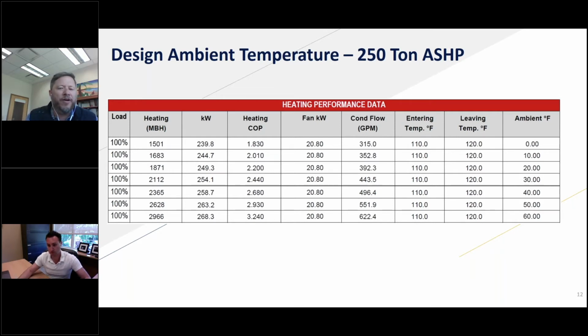The driver there is that if I'm trying to make 120 from 60, I have a lot less work to do than if I'm trying to take 0 to 120. So there's a lot more work involved. The other thing you look at there, and this comes back to when I talked about flow design before, is our condenser flow. If I fix my delta T and evaluate this at 110 in and 120 out, then at that 0 degree ambient, with about half my capacity, I have about half the flow rate available: 350 GPM versus 622 GPM at 60 degrees. So when we think about how we design systems, that's something we really need to understand, not only from a system perspective, but from a machine perspective.